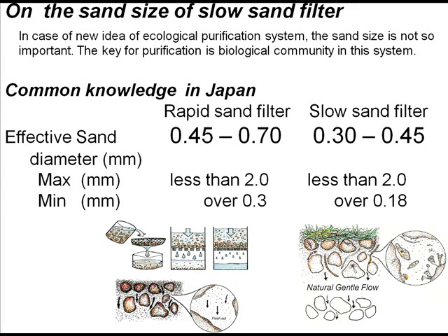On the sand size of slow sand filter, in the case of a new idea of ecological purification system, the sand size is not so important. The key for purification is the biological community in this system. Common knowledge in Japan: the effective size of sand diameter for rapid sand filter is 0.45 to 0.7 mm. However, the size for slow sand filter is almost half, at 0.3 to 0.45 mm.